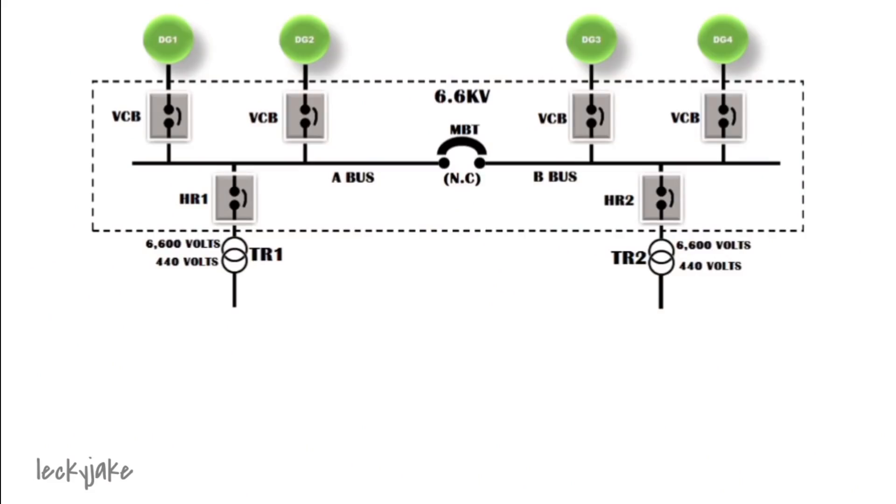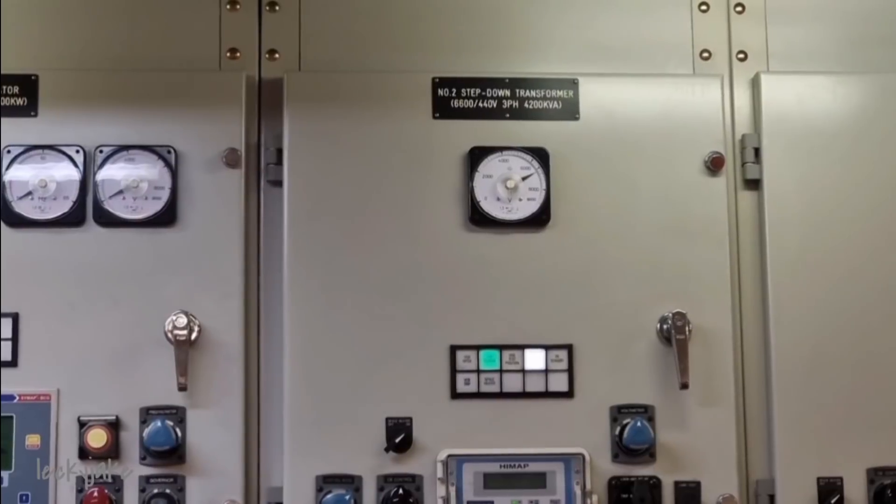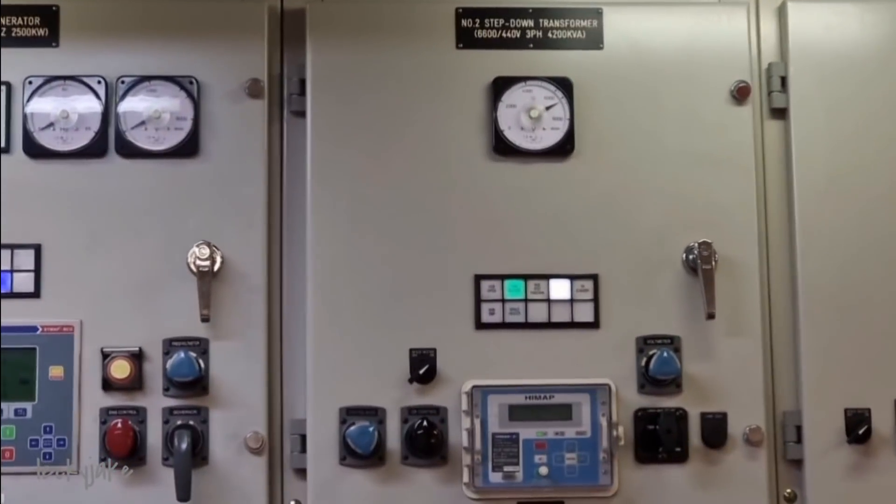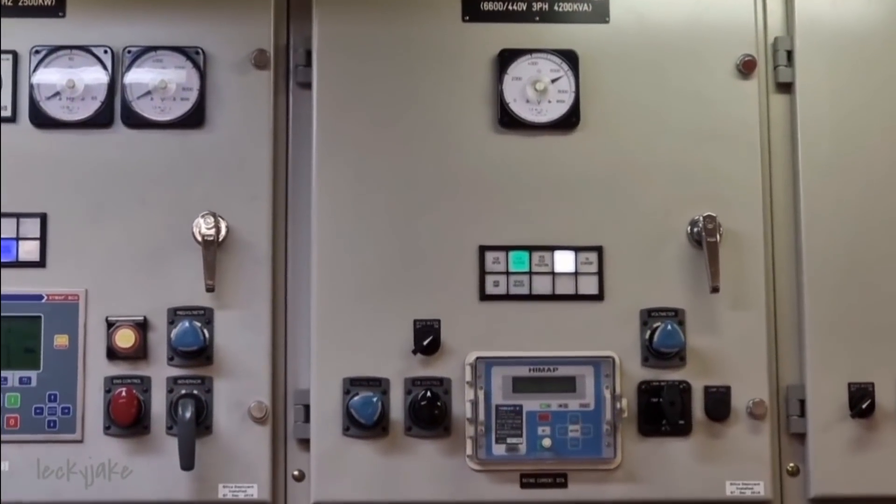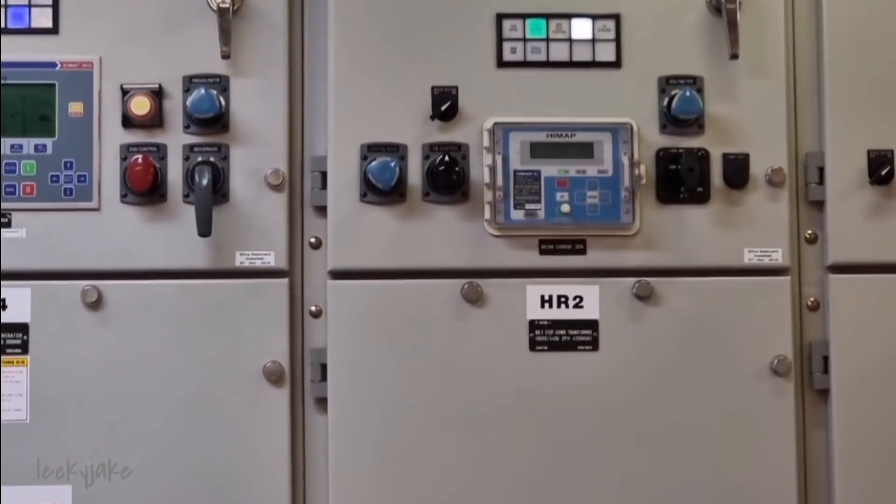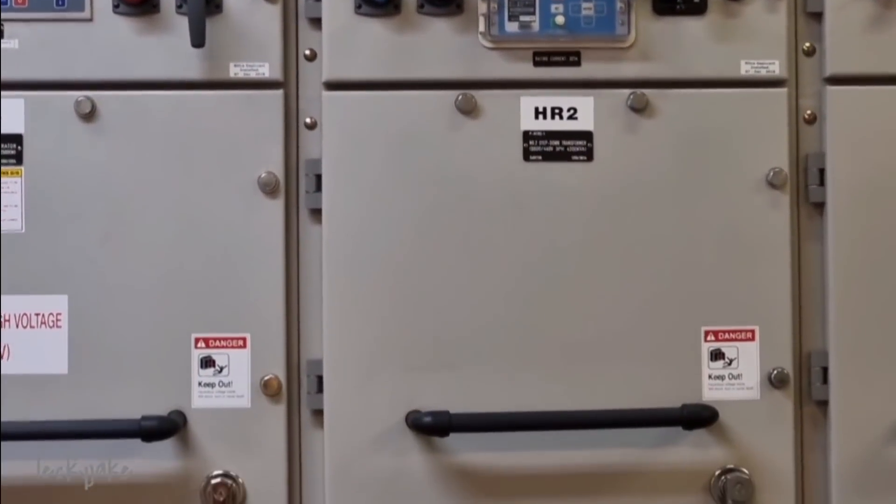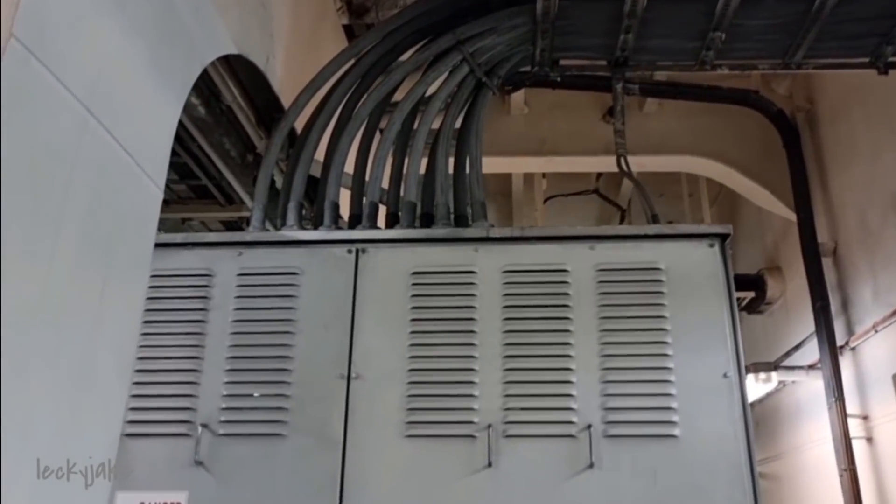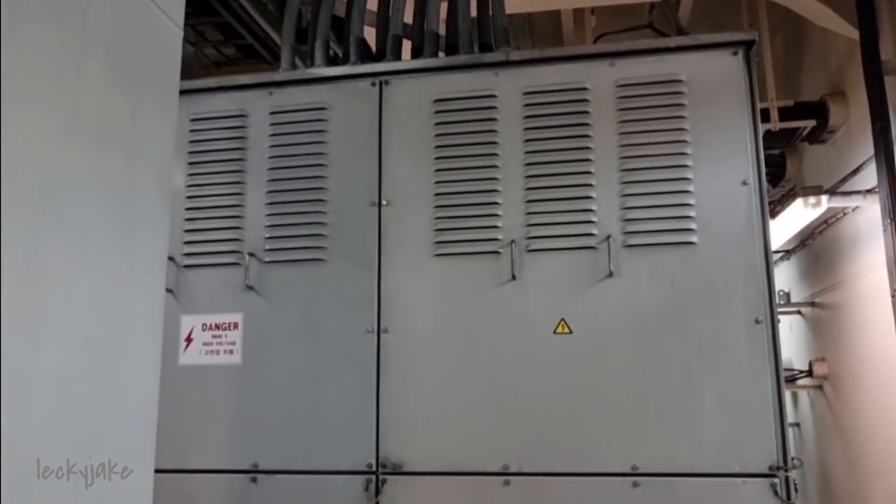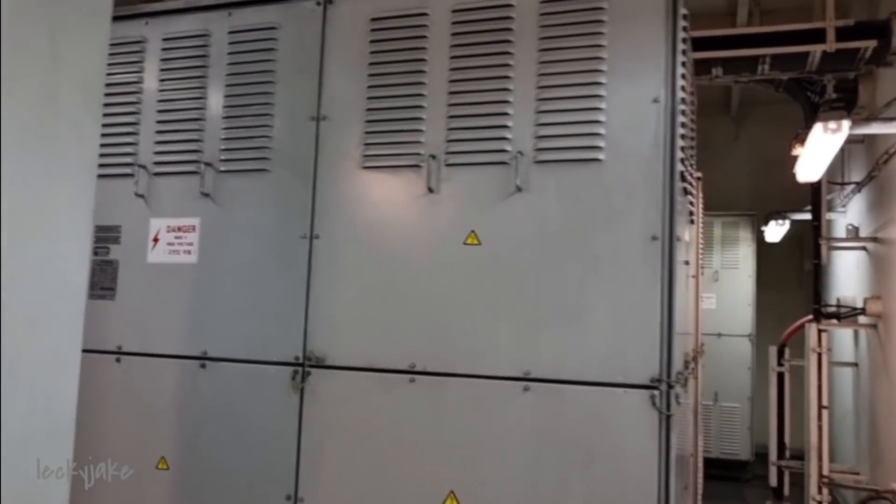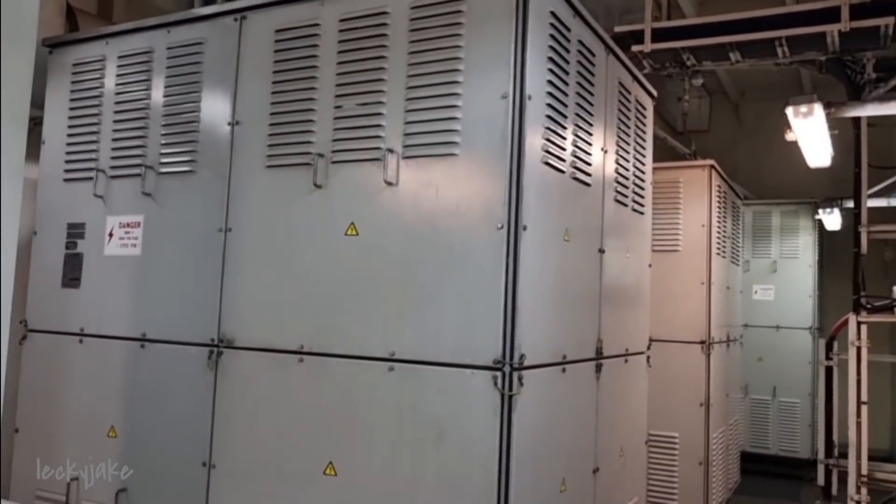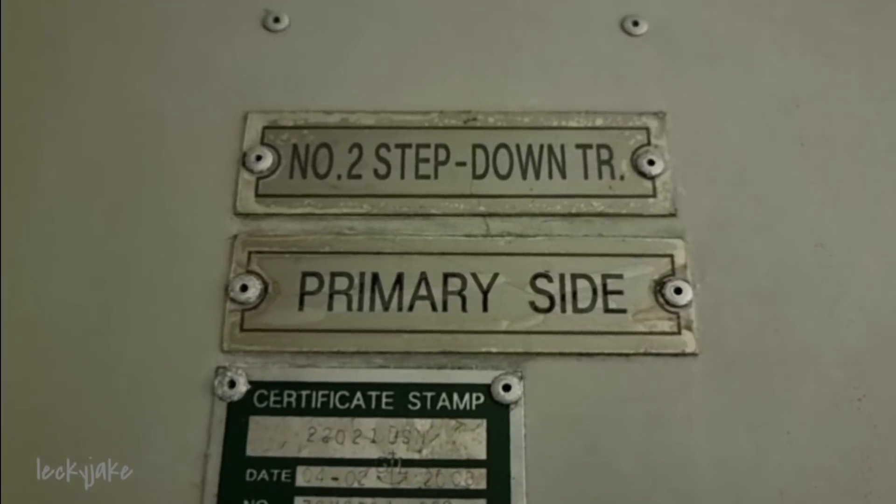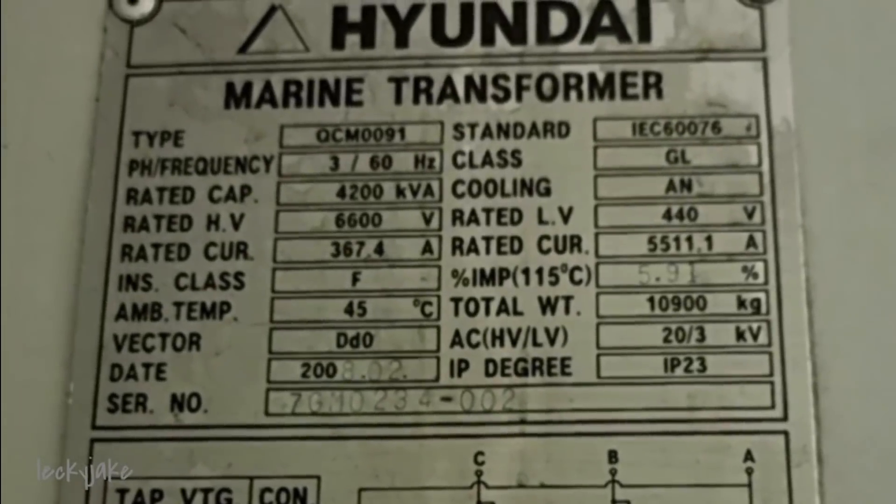The 6600 volts at the main switchboard is transformed down to 440 volts via two 6600 to 440 volts 4200 kVA transformers. This is to supply the main switchboard 440 feeder section. So this is how big the transformers which are located at the side of the engine control room.